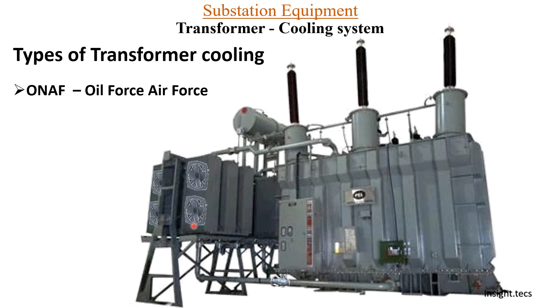An oil force air force cooling system will look like this — on the back of the radiators you will have fans placed, and there will also be a provision of a pump to circulate the oil inside the transformer. Transformers of about 100 MVA to 150 MVA capacity use this kind of cooling system.